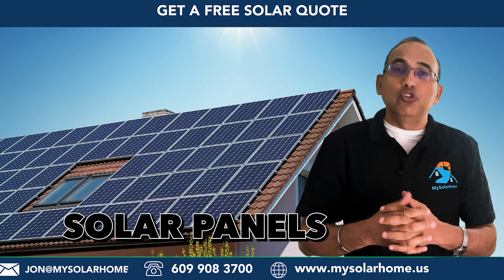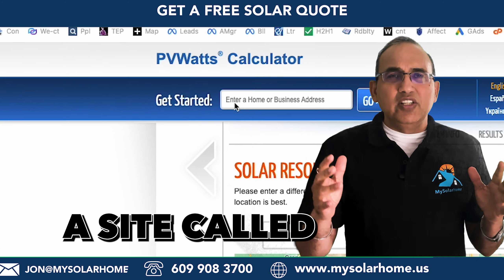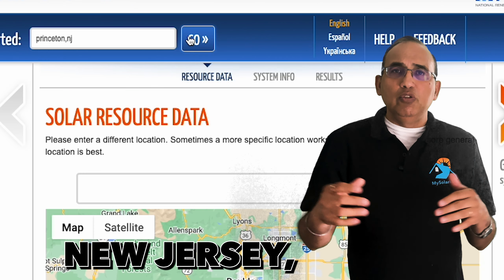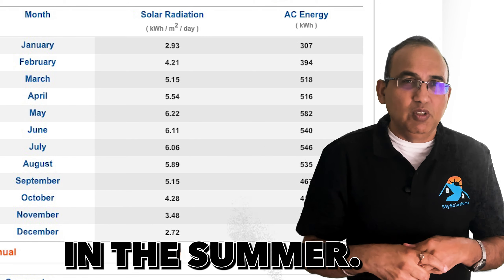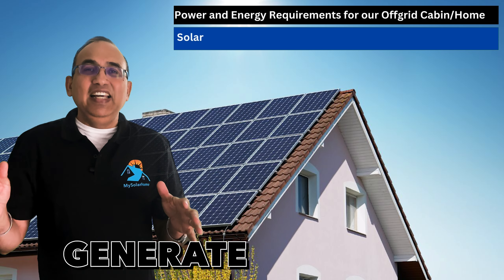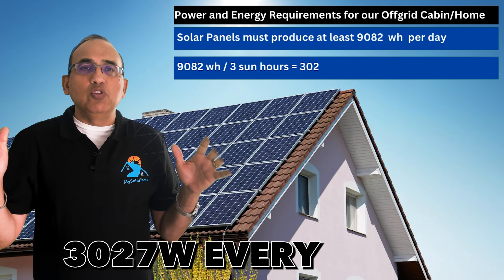Finally, we size the solar panels. We need to generate 9,082 watt-hours every day to fully charge the battery for two days of autonomy. Most regions in the US get three or more hours of full solar insolation per day. There's a site called PV Watts where you can measure sun hours by location and month. For example, Princeton, New Jersey has a minimum of 2.72 sun hours in December, going up to six hours in summer. For our calculations, we'll assume at least three hours of solar radiation daily.